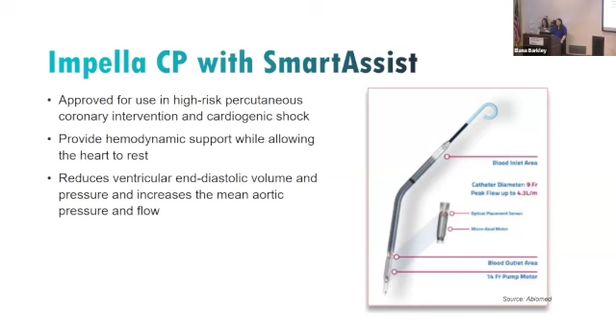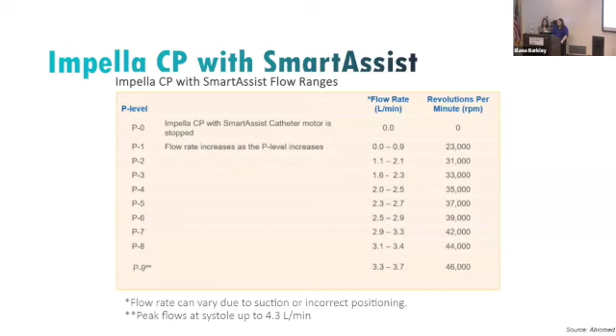And here's a slide with the P-levels. With the P-levels, you can adjust what's called the performance level, and then you can adjust the flow, which also gives you a higher cardiac output. The more revolutions per minute, the higher the flow you would get. With the CP, the highest flow you can get is about 3.5 to 3.7.